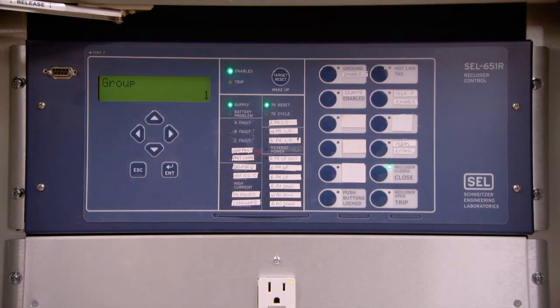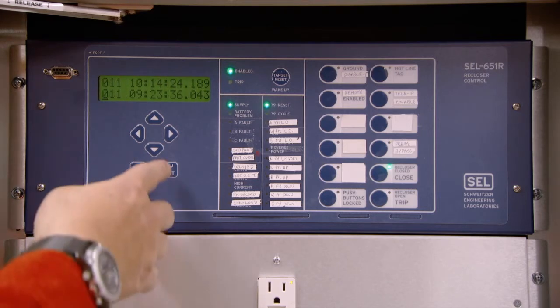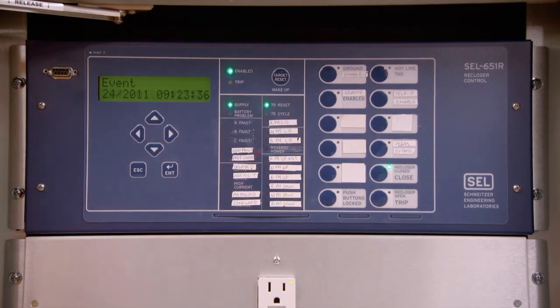To return to the initial window of logged events, press Enter to navigate to any of the 50 logged events in the system. If you want to select the next event down, press the down arrow key to highlight the event. The screen will now show two events, the one at the bottom being the second last operation. Again, if you hit Enter on the selected event, you can now go through the same procedures as you did for the very first event.